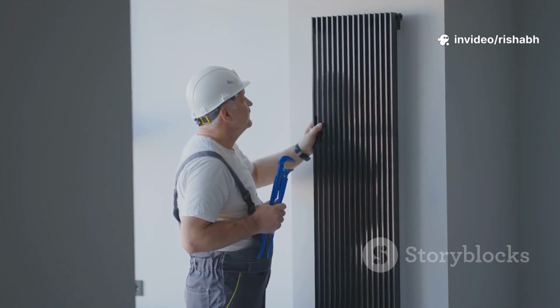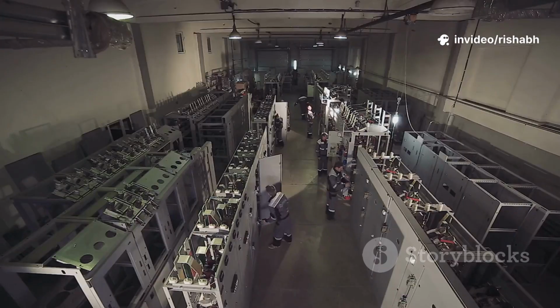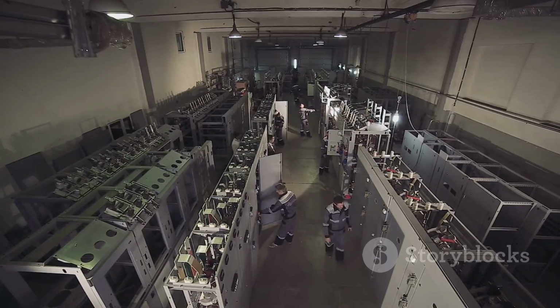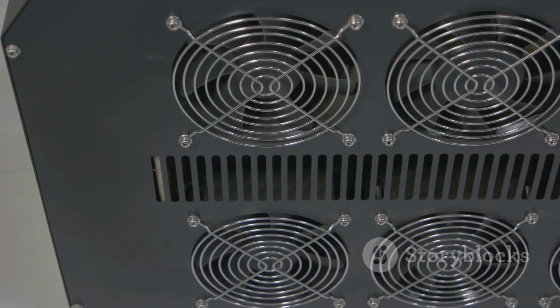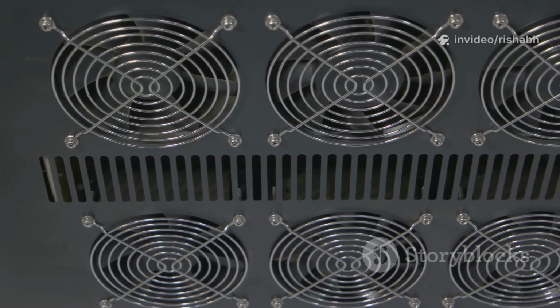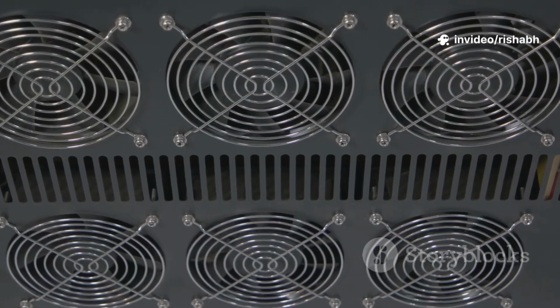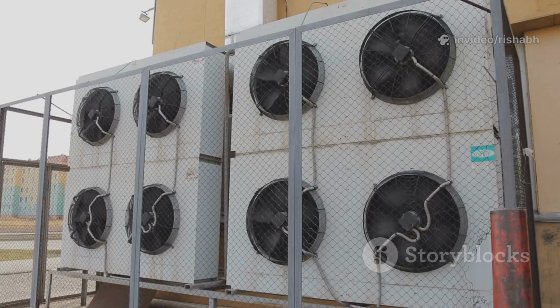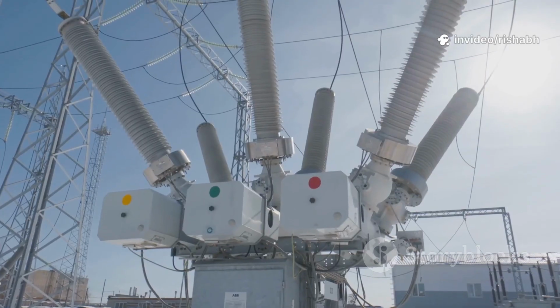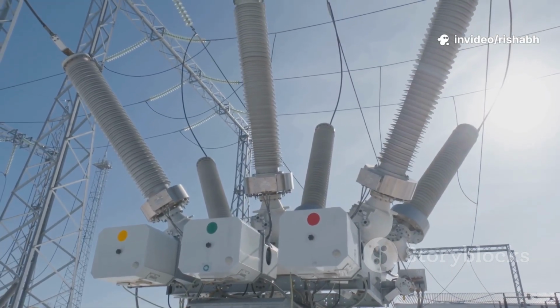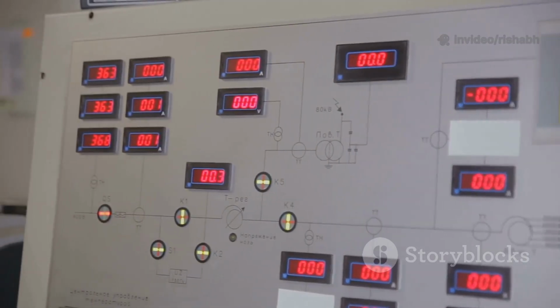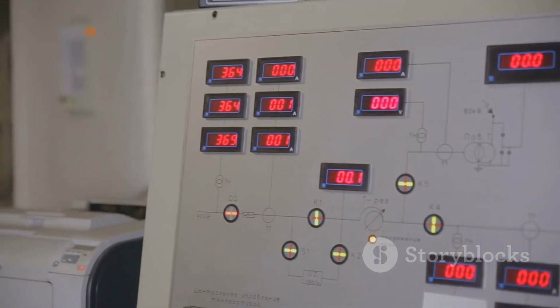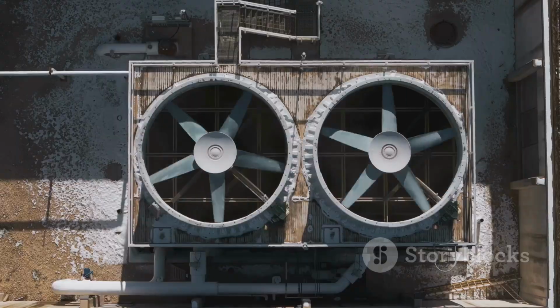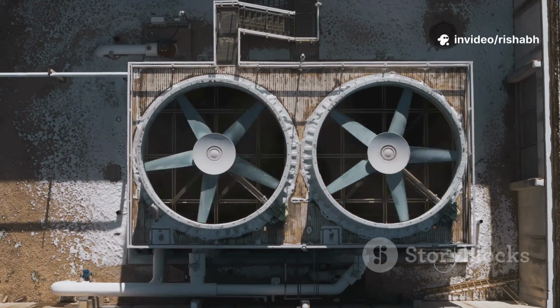To increase the cooling capacity, we can add fans. This method is called ONAF, or oil natural air forced. The oil circulation is still by natural convection, but powerful fans are mounted below or beside the radiators. These fans blow a large volume of air across the radiator fins, forcibly convecting the heat away much more effectively than natural air movement. This allows the transformer to handle a higher load without overheating. An ONAF-rated transformer will have a base ONAN rating and a higher ONAF rating when the fans are running. The fans are typically controlled automatically by temperature sensors.